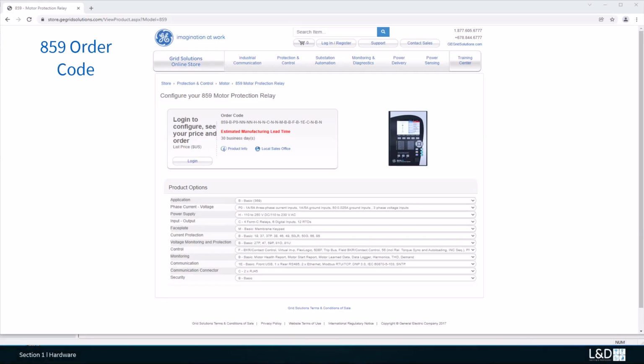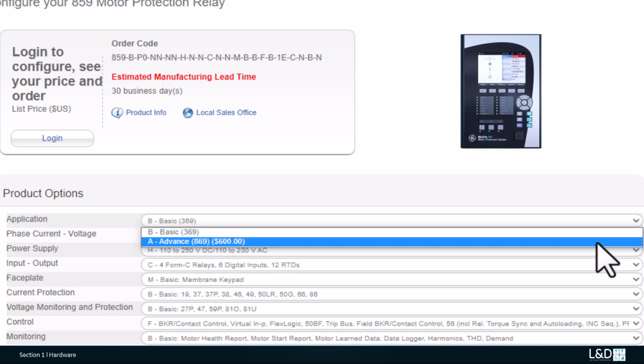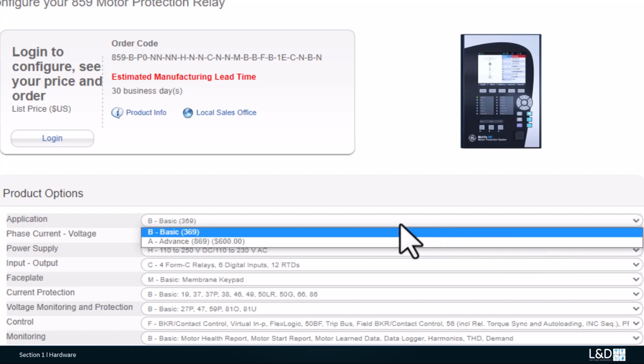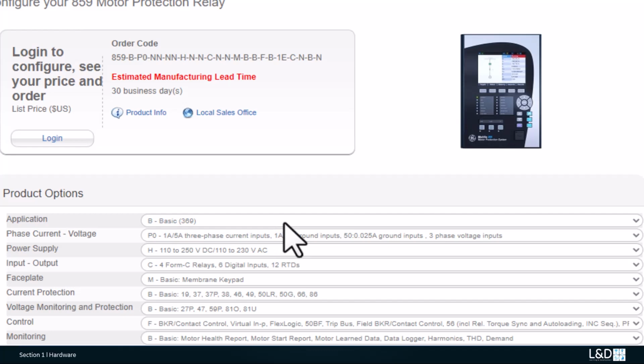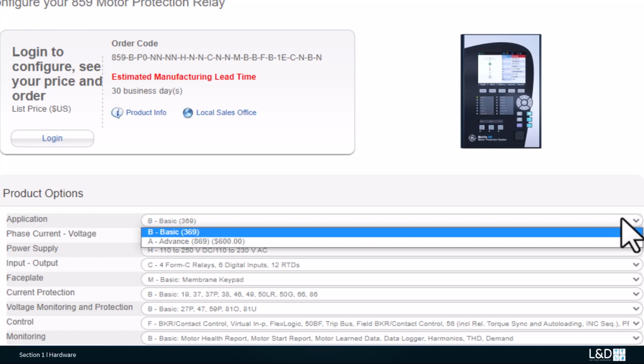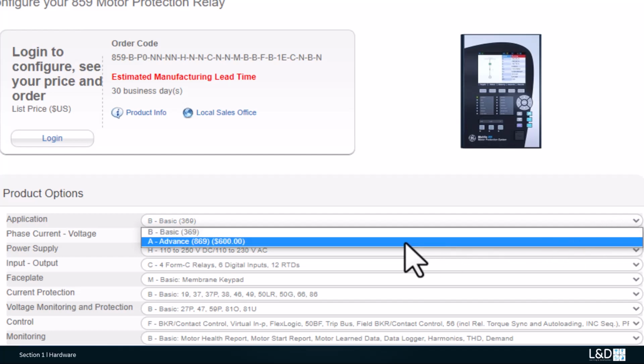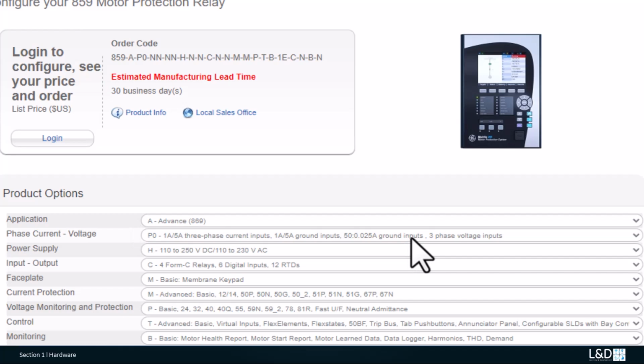The order code of the 859 is simplified into the basic 369 or the advanced 869, two applications with the suffix B and A after the 859. So when 859B basic is selected, this automatically defaults all the options to the basic, which are equivalent to the fully loaded 369 relays. When the selection is set to A, advanced 869, this allows users the option to add advanced features like what we have in the 869, such as motor ESA or advanced cybersecurity options.